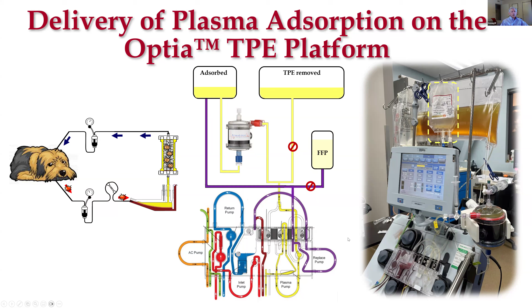So we've got the animal's contaminated plasma coming into the device. The output of the plasma coming out of the device then goes up into this small blood bag, and then the return plasma comes out of this bag back to the patient. So we're using the patient's own purified plasma to serve as the replacement solution. That's a pretty easy setup to do, and we use this little interim bag because the remove pump and the return pumps don't always work at the same flow rates, so you need a little bit of a reservoir of plasma in there so that the bag doesn't suck air.